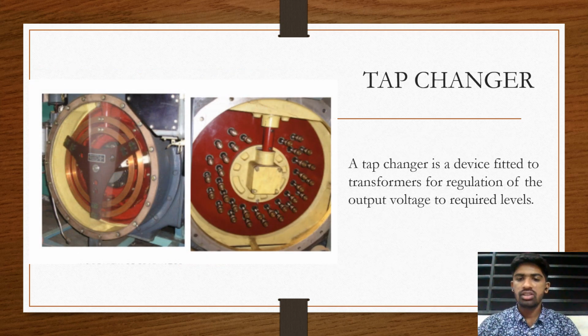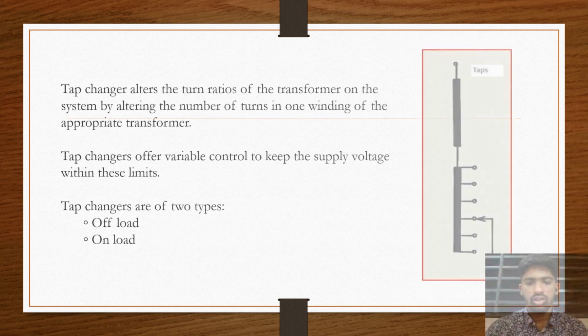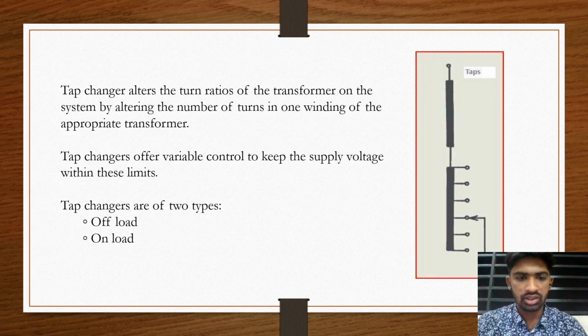Getting into the tap changer, a tap changer is a device that is fitted into a transformer for regulating the output voltage to required levels. To know briefly how a tap changer works, we have a short picture on the right side, and all those pointy antenna things are called the taps. The tap changer alters the turn ratio of the transformer by altering the number of turns in one winding of the transformer. To change the number of windings, we have to select each tap, and by changing the taps, the number of windings may increase or decrease accordingly. These tap changers offer variable control to keep the supply voltage within the limit, and each tap has its own limit. One tap has a limit of about 20 volts, and the other tap will start from 20 and go till 40, and each tap has its own.